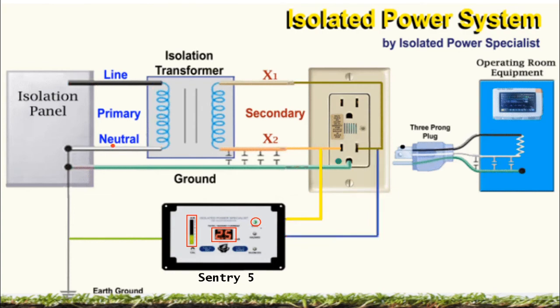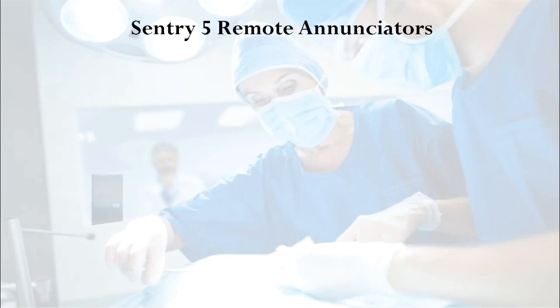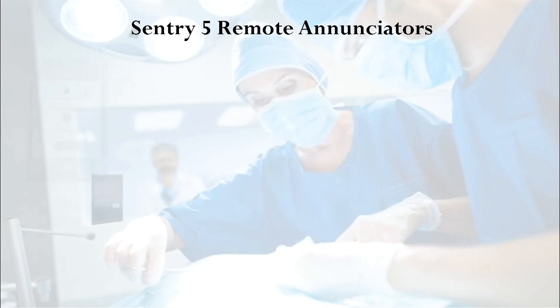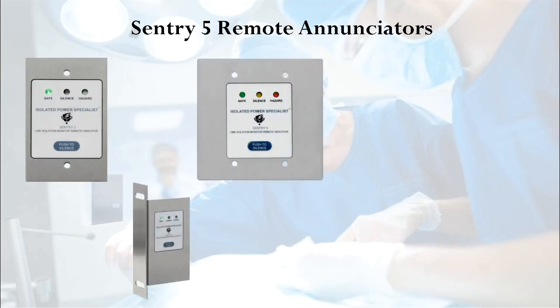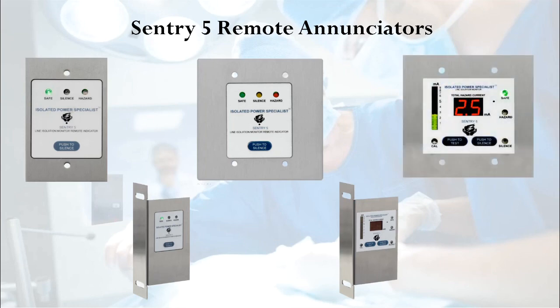Now, our last point. What if the line isolation monitor is mounted in a room other than where the work is being performed? In that case, we need a remote annunciator, like this one. This is a single-gang remote annunciator that has three criteria stipulated by the NFPA: the green light, the red light, and the audible alarm. However, Isolated Power Specialists makes various types of remote annunciators — single-gang panel-mounted, double-gang panel-mounted with digital display, double-gang with digital display, and many others.